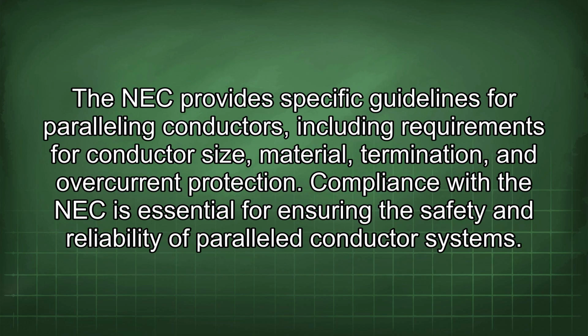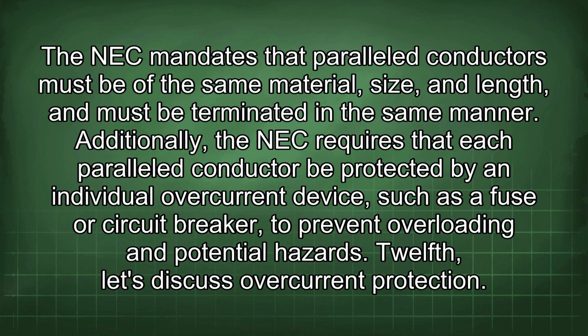The NEC provides specific guidelines for paralleling conductors, including requirements for conductor size, material, termination, and overcurrent protection. Compliance with the NEC is essential for ensuring the safety and reliability of parallel conductor systems. The NEC mandates that parallel conductors must be of the same material, size, and length, and must be terminated in the same manner.